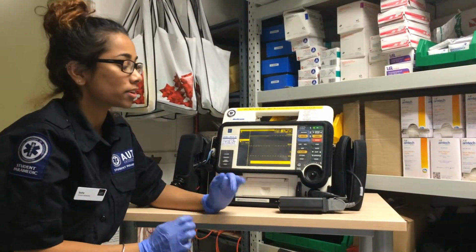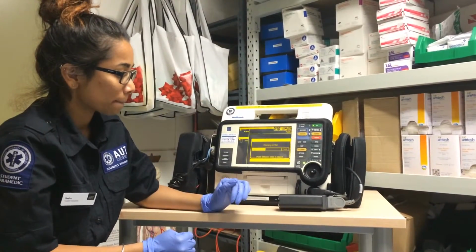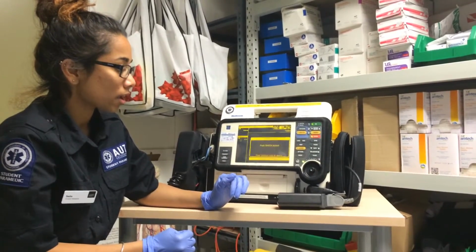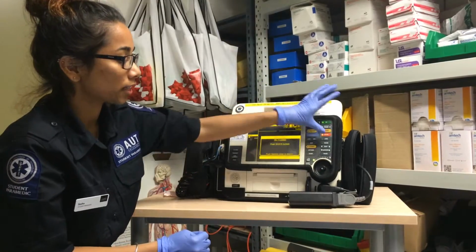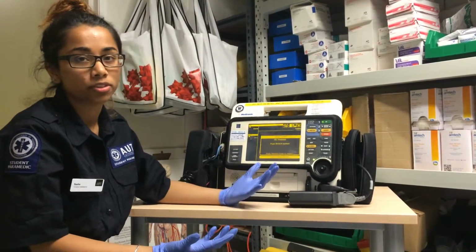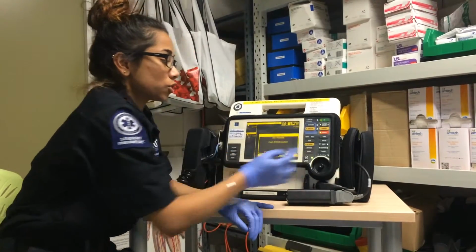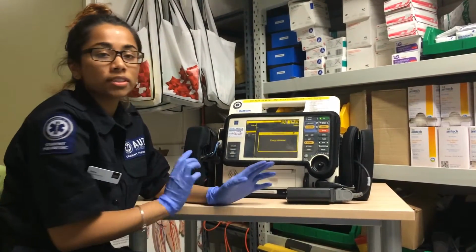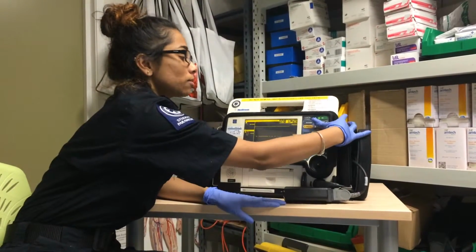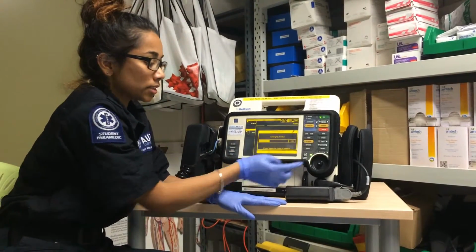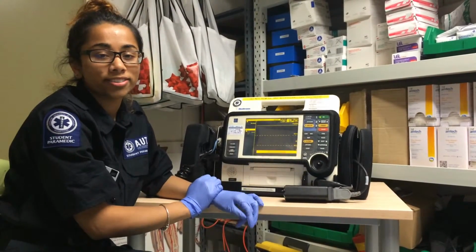And we also then want to charge the machine. So you would click the orange charge button, and once the charge is ready to be administered, you want to then click the red shock button, and it will administer the shock. So everyone stand clear, and the shock will be administered. So to disarm the shock, it's a similar technique. You want to charge the machine once again. But to disarm it, you just click the select button like so, and it will disarm the charge.